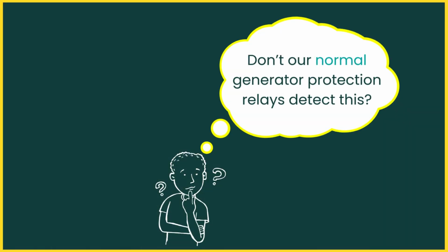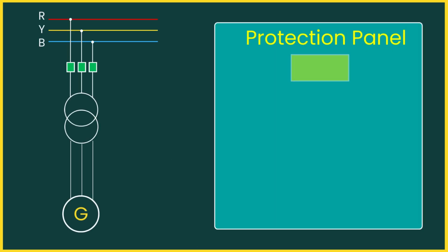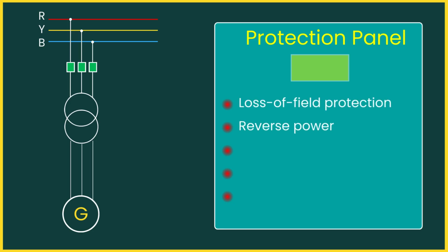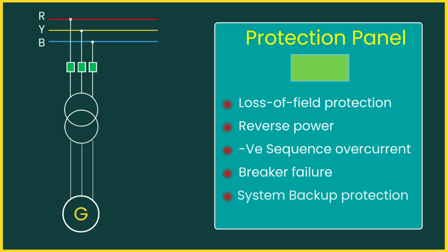But you might ask, don't our normal generator protection relays detect this? Here is the reality. A typical generator protection system includes 5 elements that might detect inadvertent energization: loss of field protection, reverse power, negative sequence over current, breaker failure, and system backup protection. However, their ability to detect dead machine energization is often limited. These relays are usually disabled when the generator is offline, as we saw in the incident earlier, or they operate too slowly to prevent serious damage.